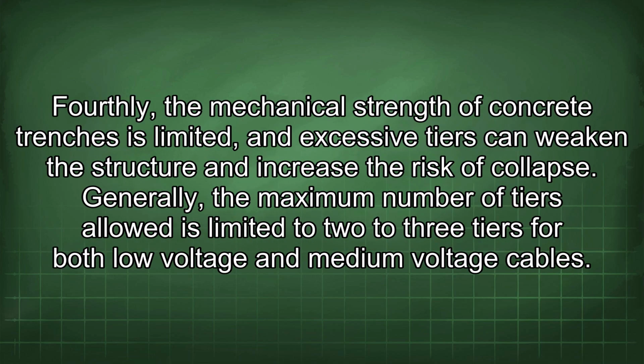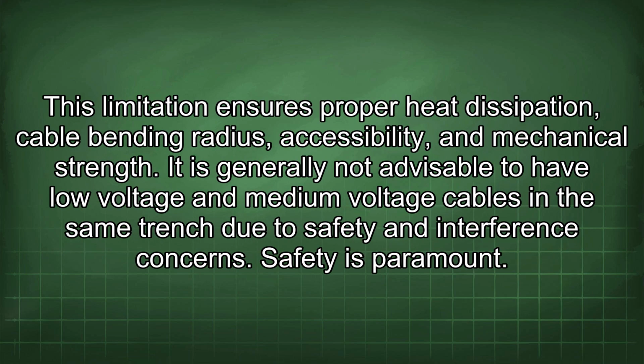Fourthly, the mechanical strength of concrete trenches is limited, and excessive tiers can weaken the structure and increase the risk of collapse. Generally, the maximum number of tiers allowed is limited to 2 to 3 tiers for both low voltage and medium voltage cables. This limitation ensures proper heat dissipation, cable bending radius, accessibility, and mechanical strength.